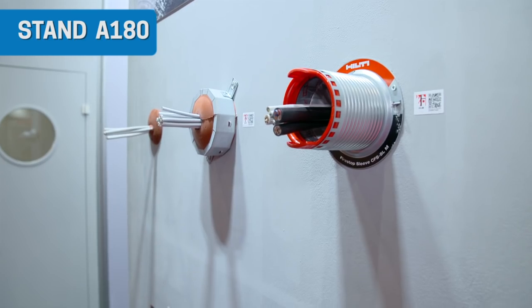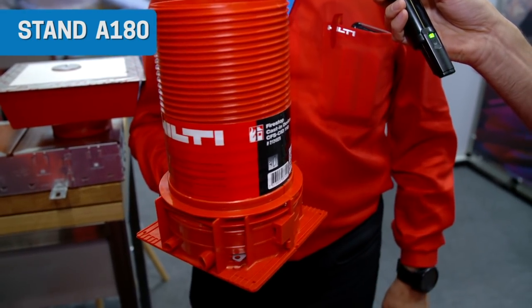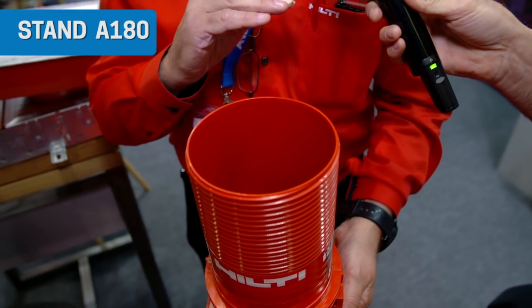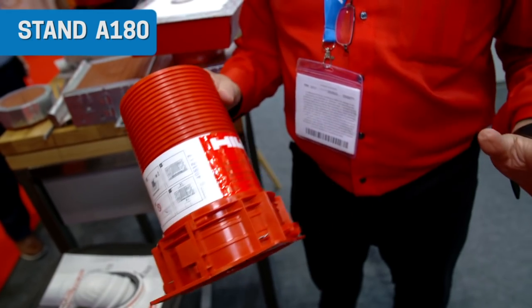For new build, this is a cast-in device. Traditionally, when you're putting pipes through a concrete slab, you pour the concrete, someone cores a big hole in it, puts a pipe in, and then refills it — which seems kind of backwards. This is a device that you put on the former, pour the concrete around it, take the lid off, and just pass the pipe through. No coring needed. You don't even need to fire stop it separately because it contains the fire stop — it's all done in one go.